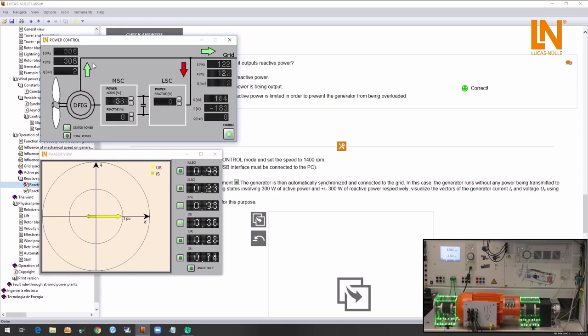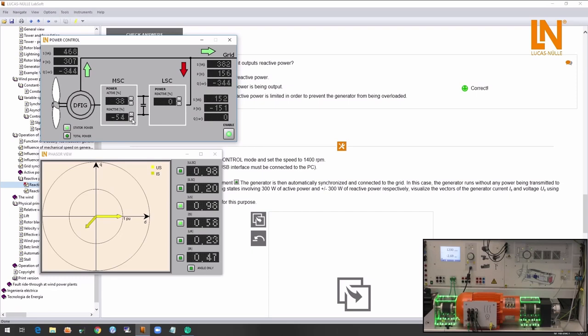Arrows are used to indicate the flow of power within the various components. Increasing the excitation via the machine side converter beyond the rated excitation causes the generator to supply the grid with reactive power. The generator then acts like a capacitor.